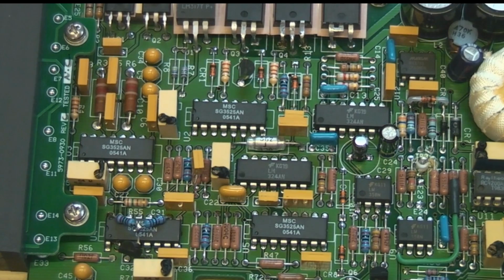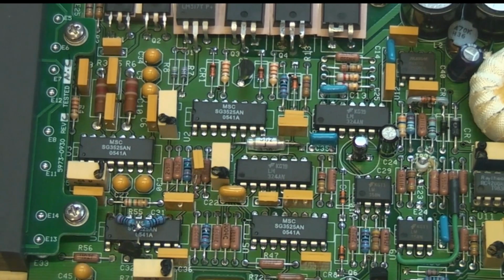The electronics on here look pretty straightforward. There's just some power supply stuff. There's some SG3525 regulators, so there'll probably be one for the main high voltage source, possibly one for the filament supply, and maybe also, because microfocus tubes have an electron gun type arrangement, another supply for some of the electron gun potentials. Actually thinking about it, this block here might be for generating some of the intermediate voltages for the electron gun. Apart from that, it's just some analog stuff, to measure beam current and possibly output voltage. All fairly standard analog stuff, so nothing particularly surprising.